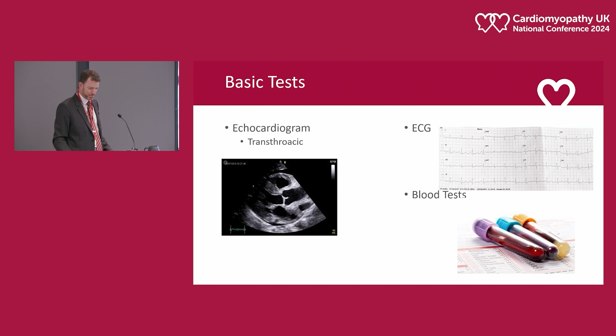All right, so a couple of things about echocardiograms. Of course, we use ultrasound, so they're pretty clever echoes. That little probe at the end is not just beaming out one beam of ultrasound. That little square has got a grid of around 64 tiny piezoelectric transducers. And essentially, when you put a high voltage through a piezo transducer, this tiny crystal, it will vibrate at megahertz levels, about 3 million times a second, like this buzz.